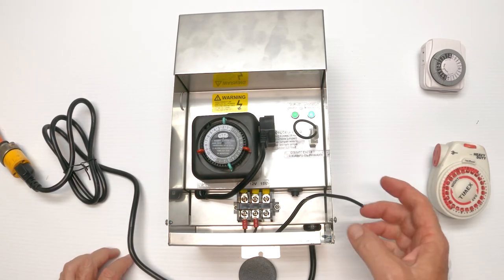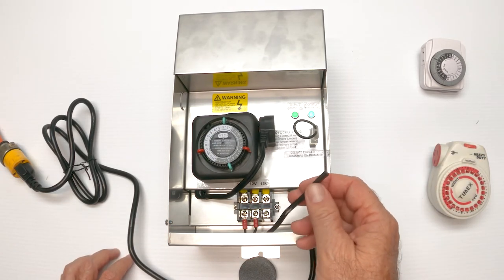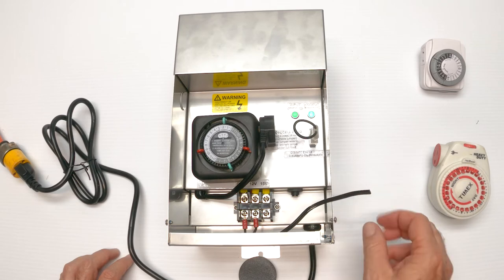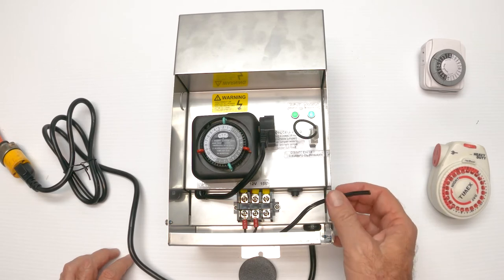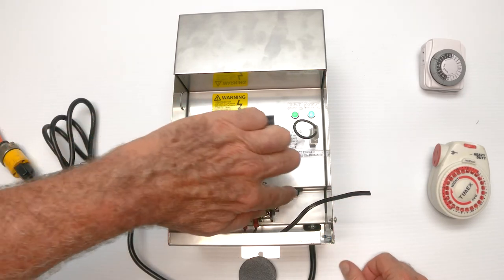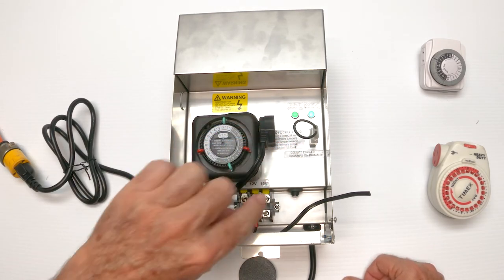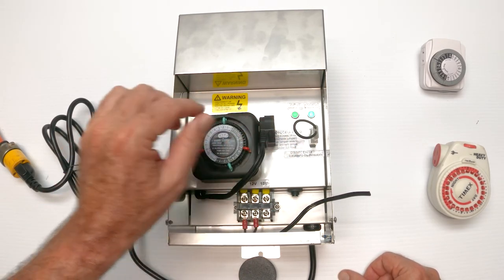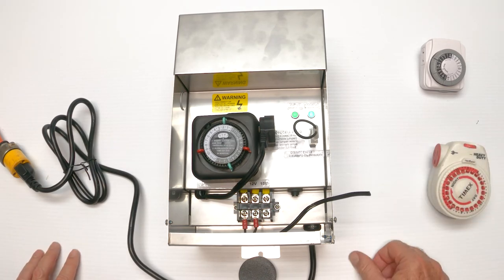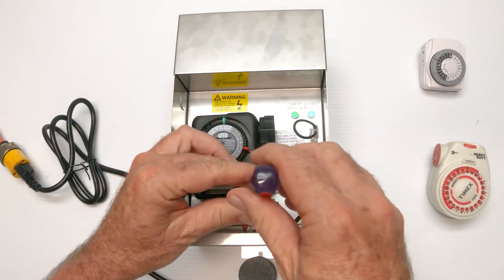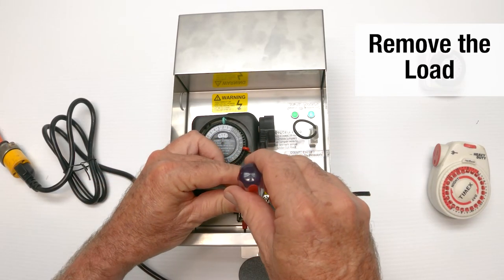Everything's working, but there's no lights coming on. We have a couple of possibilities. There's a short out in the field, and if there's a short in the field, there's a good chance the breaker down here will pop out. Not all the way out. It'll just pop out a little bit. And when you press it back in, it may wait a while and pop back out again. So what really needs to happen here to test everything is you need to get onto the terminal bus down here.